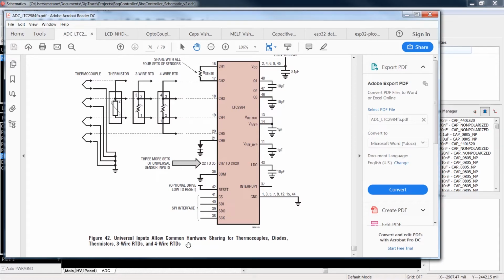I don't know why they didn't mention 2-wire RTDs, since it also supports that, but I guess they're running out of room. Basically it takes about 4 channels, and you can put a thermocouple, a thermistor, 3-wire RTD, 4-wire RTD, or a 2-wire RTD on it. I'm not sure why it's not listed, but again, probably just running out of room. Since this chip has 20 inputs, you can put 4 of these per chip, and that's what I've done.